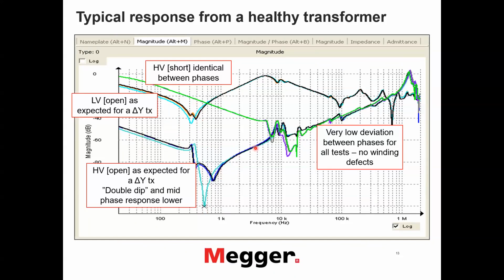But otherwise, when we go to the high frequency range, we see that all phases go practically the same for a given type of measurement. Here we have open circuit measurements, then we have a short circuit, the green one, which is on top. So we also see pretty much similar phases and windings. Then we have the low voltage winding, also measured at open circuit conditions. Similarly, we have three phases on the high voltage side and low voltage side, pretty much the same. And this is the case where we can use a comparison and see that it's very fine.